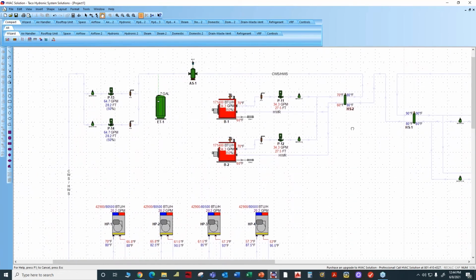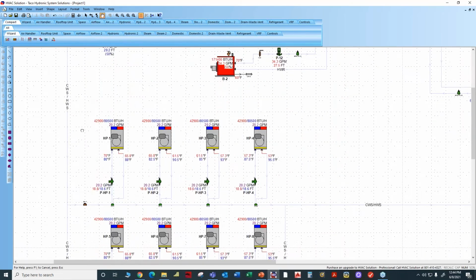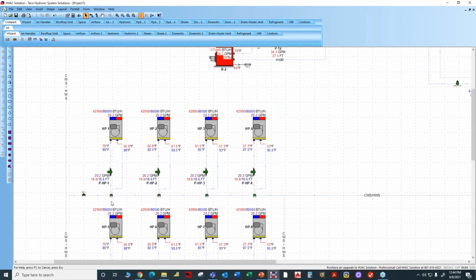But anyway, if we follow the loop around, let's say here are the secondary pumps. The secondary pumps are sending the water to the water source heat pumps, and we're using a single pipe system. So we're using a load match circulator to send the water to the water source heat pump. The water source heat pump is acting like a fan coil within the space. So it's actually supplying either cool air or warm air, cool air for the summer, warm air for the winter.